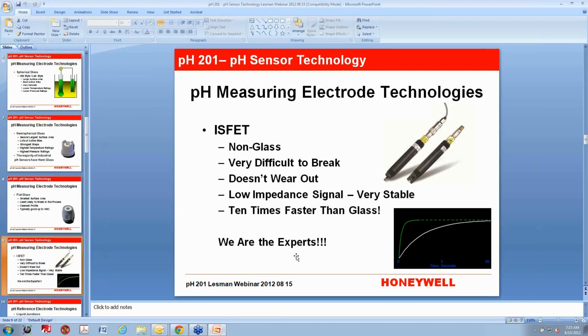And the really slick thing is it's about 10 times faster than glass, and that's what this little diagram is in the bottom right-hand side. That green line is a FET sensor. The white line is a good quality glass pH sense electrode, and they were both put in a buffer at the same time, and you can see how quickly the green line gets up to the actual buffer value. It takes about a second for the FET to get to its value when it's brand new. For a brand new pH sensor with a glass measuring electrode, it takes about 10 seconds, which is not slow. That's pretty much what everybody sees, but a 1 second response time is pretty astounding.